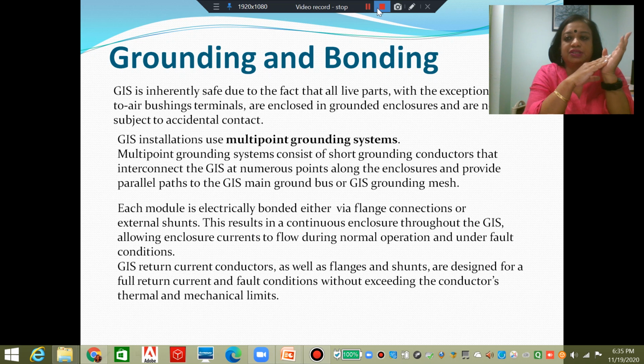What we have to remember is that in case of a GIS, the disadvantage is that we don't have a large area over which it is spread, and therefore we do not have the multiple points, the extended network of transmission lines and earthed wires and grounding rods, everything coming together, and each of these points earthed. In case of air transmission lines, it provides us a very extended grounding system, and that makes it easier to ground and safer. Because of the nature of GIS, this is not possible. However, we should still try to ensure that the GIS installation is grounded at multiple points.